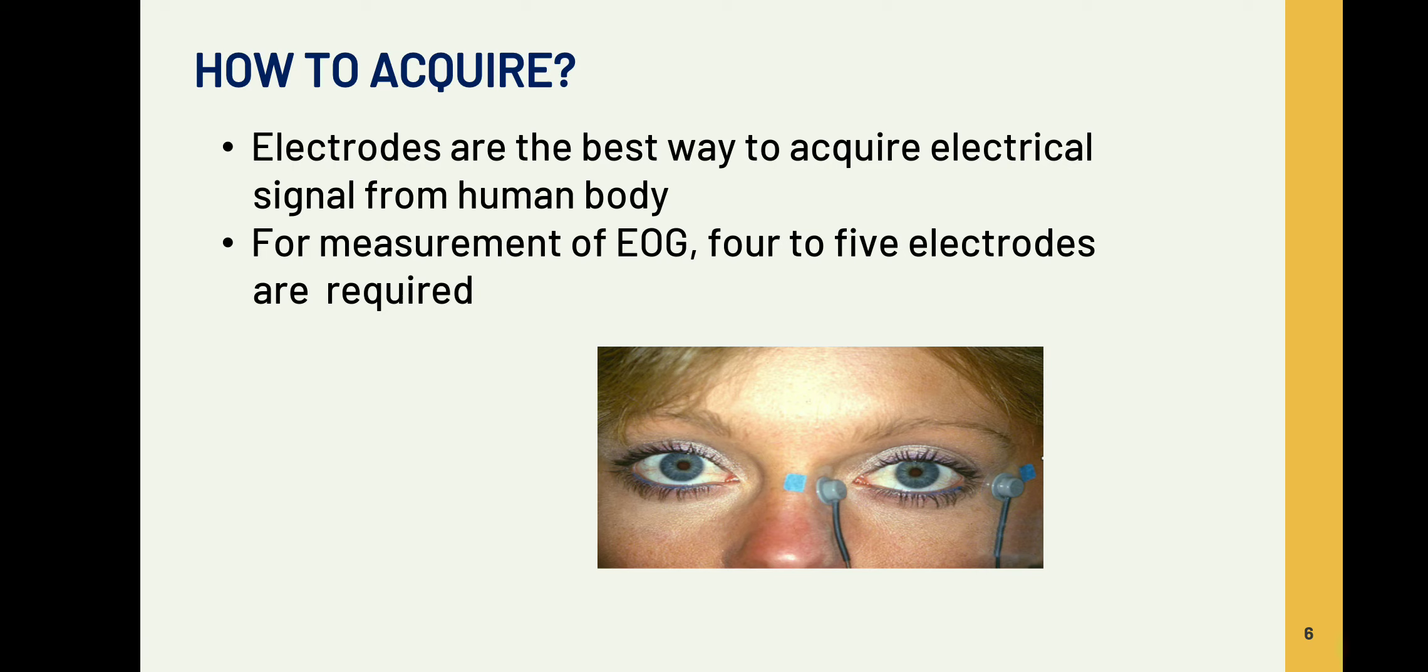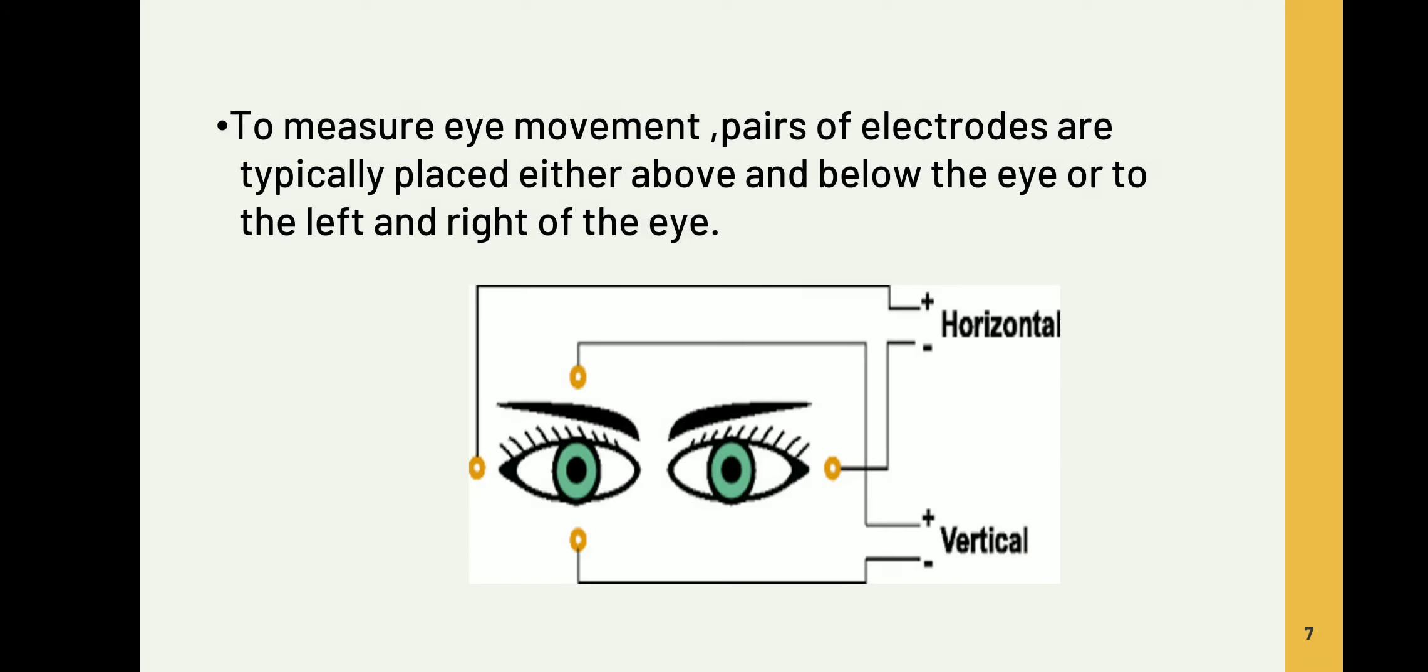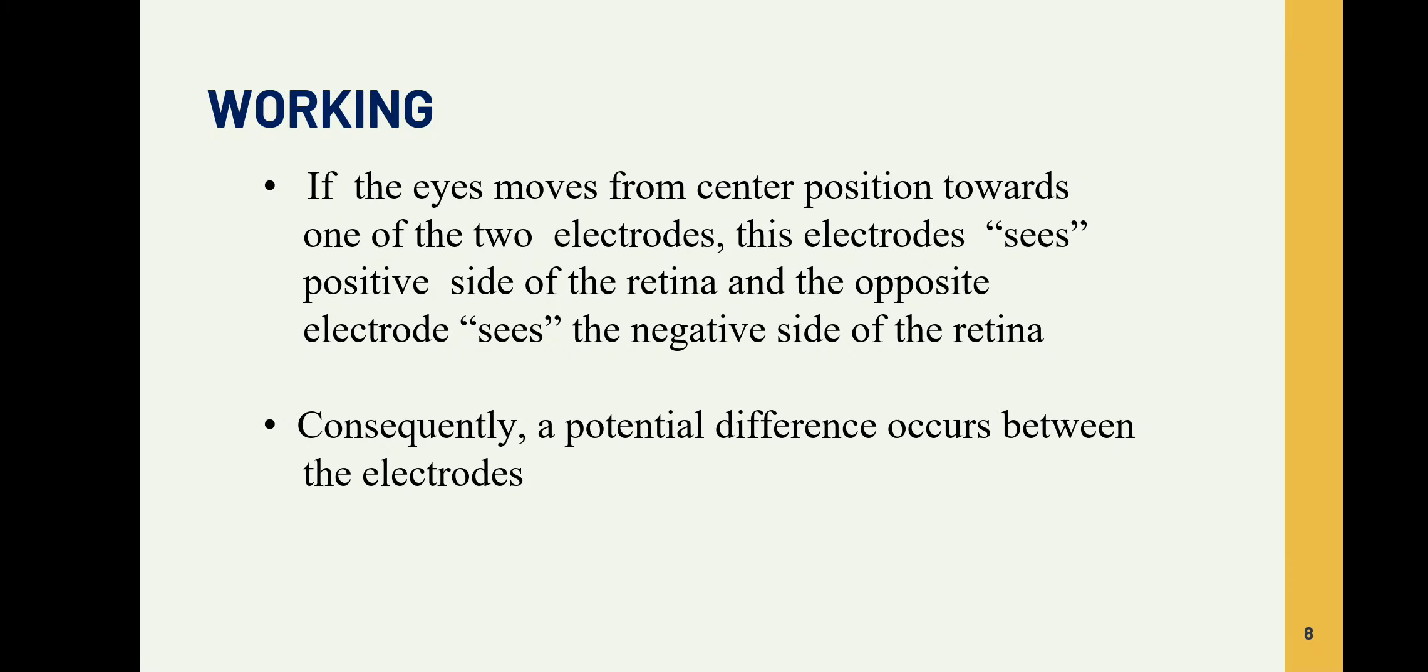Let's see what are the placements of the electrodes. For measuring the eye movement, we are supposed to place two electrodes or a pair of electrodes horizontally, that is left and right of the eye, and a pair of electrodes above and below the eye. So top and bottom two electrodes are placed, and left and right two electrodes are placed. These are the horizontal and vertical placement of electrodes.